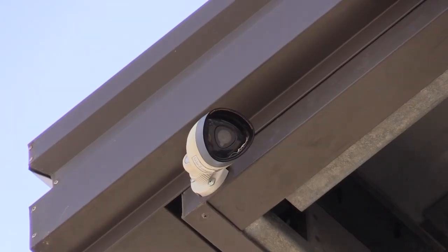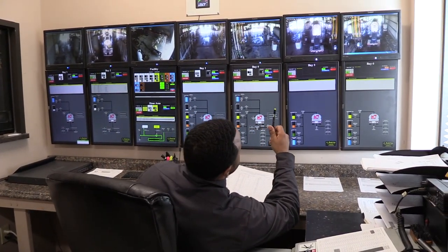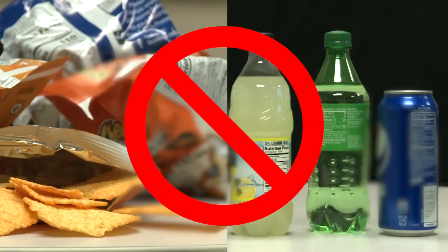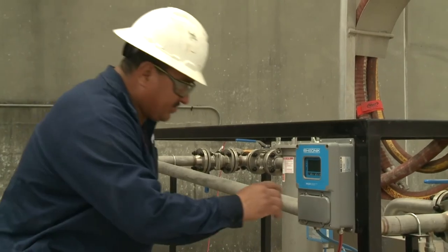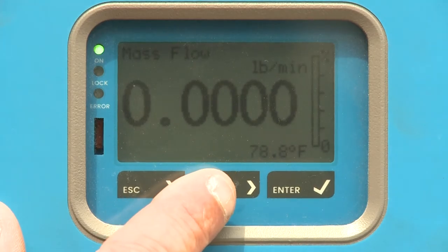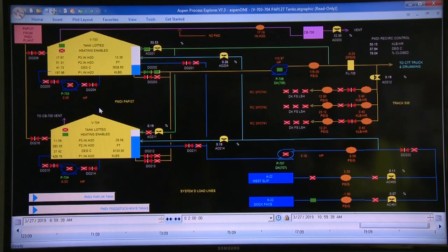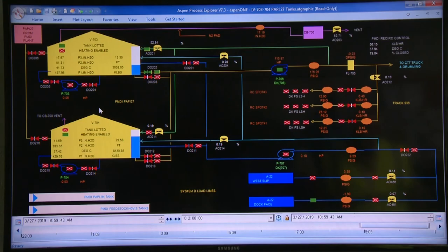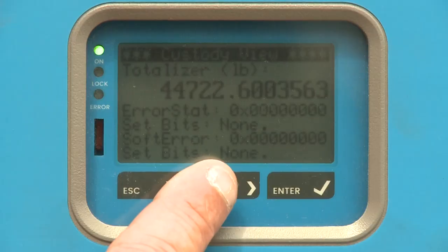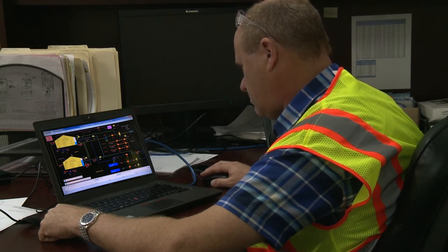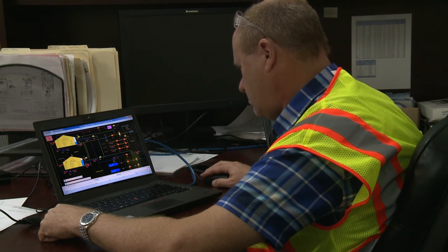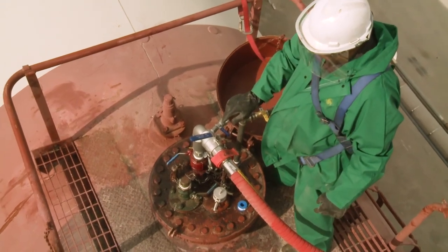Signaling systems that include surveillance equipment, such as cameras, may be used to notify people within the facility that a problem may exist so that the product flow may be halted immediately. Other safety precautions include no smoking, vaping, or use of tobacco products, and no eating or drinking in the area of the transfer process. Monitor the amount of product being transferred at all times. This can be accomplished using an inline flow meter, by watching the rail car weight if there is a scale at the unloading station, or by monitoring the level rise in the storage tank. Use of two methods of level measurement provides an additional layer of safety and reduces risk of overflow. Don't rely on automatic shutoff systems to stop the unloading process — such systems are not foolproof. There is absolutely no substitute for an attentive operator.